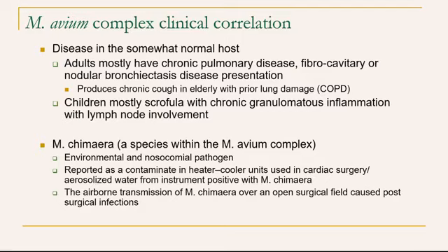The units were contaminated upon manufacturing, and when surgical centers used water and aerosolized water through these cooling units in their surgical procedures, they were found to be spraying water that was contaminated with M. chimera. So this airborne transmission of this organism over an open surgical field caused post-surgical infections. This is one claim to fame for M. chimera.